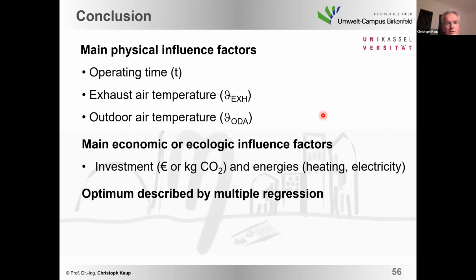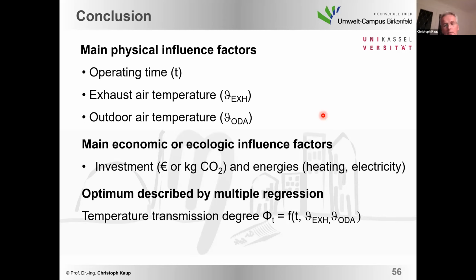And that will lead to the optimum of the thermal transmission degree, or the efficiency, as a function of all these three, and the specific fan power as a pair, as a couple. It's not possible to look only at the thermal side of the energy. We also have to take into account the link in between. So the specific fan power is following the thermal transmission degree.